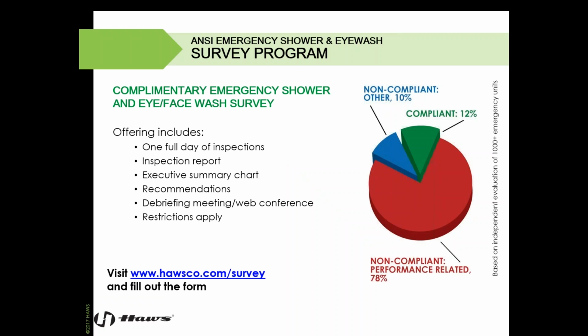Yes, as a no-charge service, Haws does offer a free survey program. We will send our sales associates out for a one-day full of inspections. What we find in the field when we've facilitated these is that 78% of the products out in the field actually are not compliant, and that's from a performance standpoint. So that could be too much flow, lack of flow, as Sam mentioned earlier, tepid water. It could be below that 60 degrees.